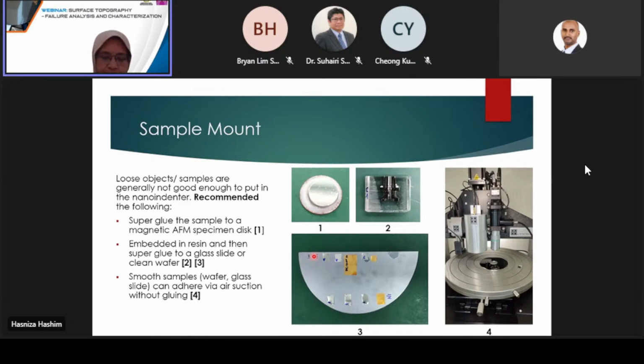There are several ways to mount the samples. We can mount the sample onto a magnetic AFM specimen disc as here, and then put it on our magnetic sample stage, or we can use the suction ring to hold a very smooth sample like a glass slide or clean wafer. If you have flexible or odd-shaped samples like bone or fiber, you probably need to embed them in some resin or epoxy, do the cross-section, and polish the surface down as shown here.